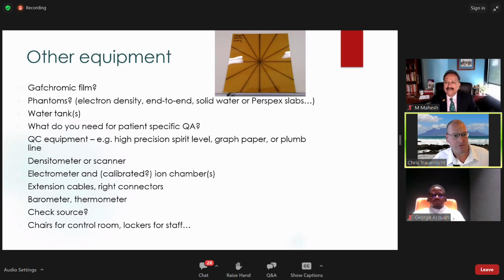You could add a high precision spirit level, and then you will need a calibrated ion chamber for absolute dosimetry. Make sure you have the right extension cables and the right connectors. Get a barometer and thermometer while you're at it. You may need a check source to check the accuracy of your ion chamber. You may even go down to, I want chairs for the control room, because my chairs are 20 years old and the wheels are falling off. If you don't ask for it, you're not necessarily going to get it. So put it in the tender or in the bid document, and maybe it gets kicked out, maybe not.